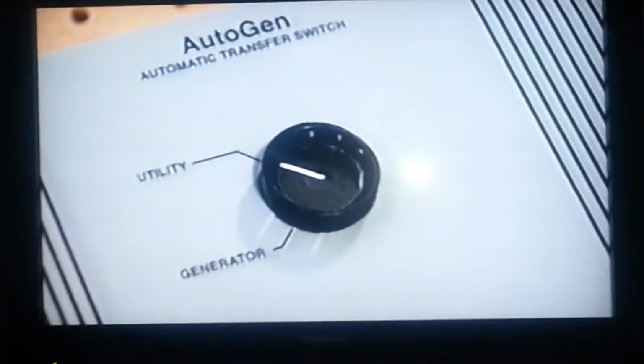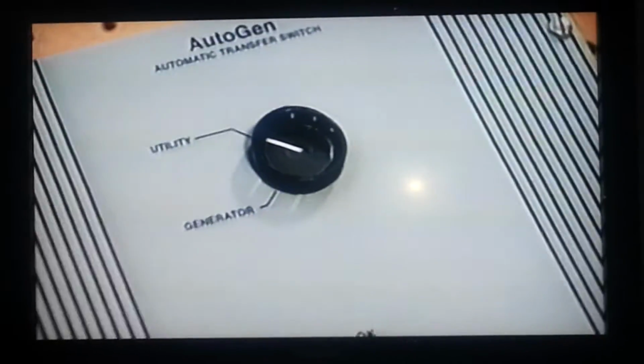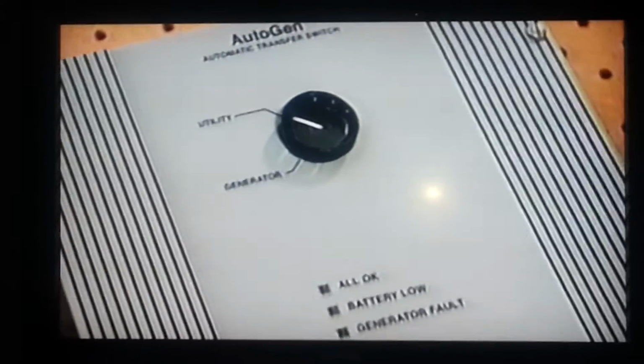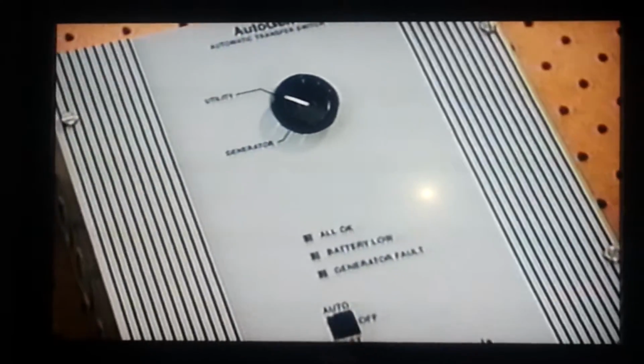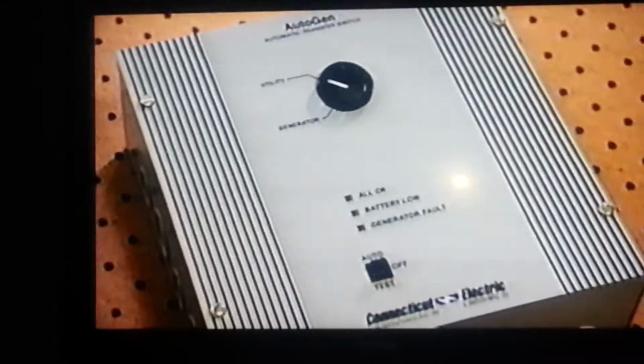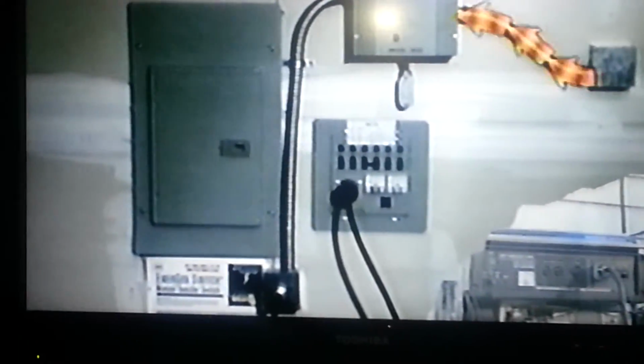The first component you will need to install is the ATS transfer switch. The transfer switch monitors power from your service panel. In the event of a power failure, the transfer switch sends a signal to the engine control to automatically start your generator. Once the generator is running, the ATS transfers the sub-panel load to the generator.